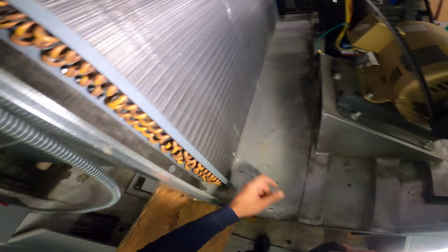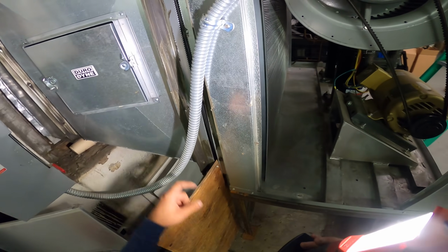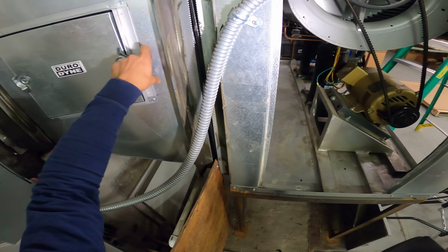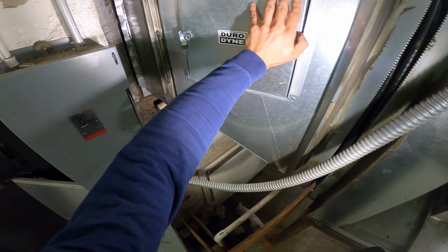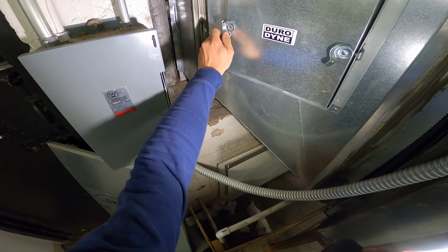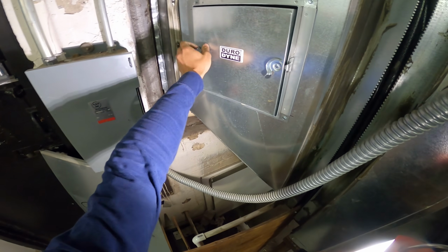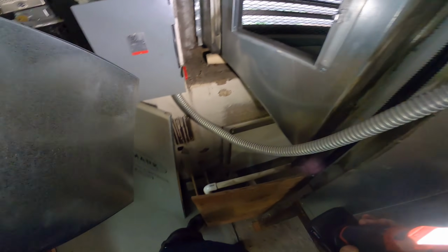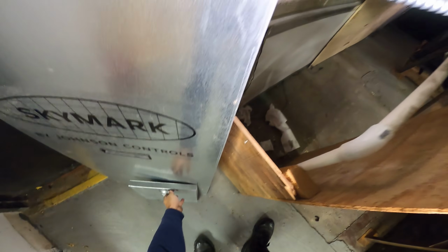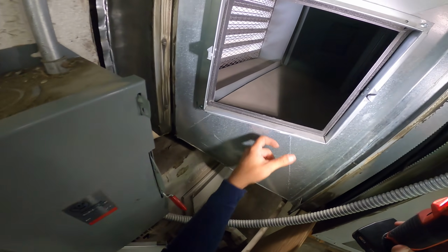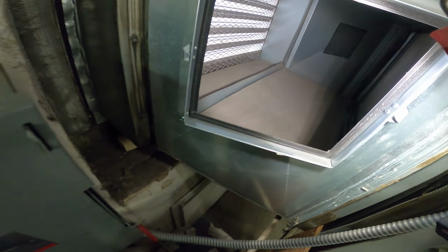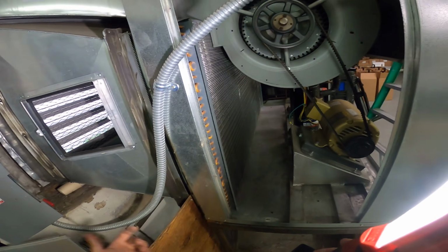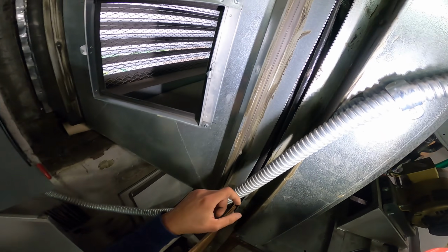One thing to note with these condensers is that it's always the side exposed to the outside air that gets dirty. So what happened is, I started this system, I think it was running on super high pressure, and there was no access. I was not able to see through here, but I knew it was dirty. So I cut in this access panel and cleaned the coil, and it looks great. I cut one on both sides so we can acid wash it, and it really worked out.